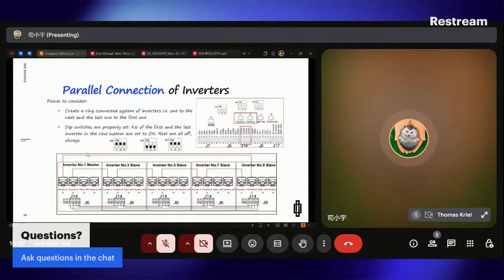And another part is the parallel cable. We need to make sure the first one's parallel B is connected to the second one's parallel A. So B to A, and the last one's B to the first one's A. And after that, we need to check the dip switch. We need to turn on the K6 on the first one and the last one's inverters. Then it will be okay.